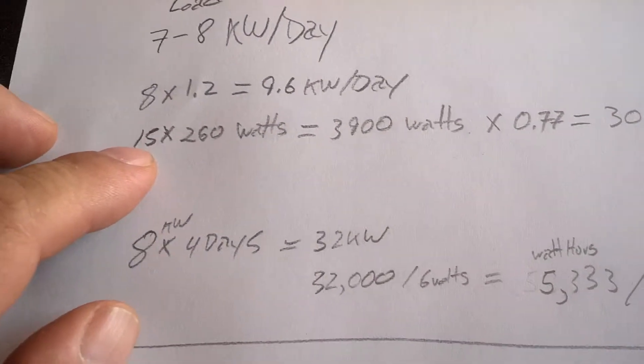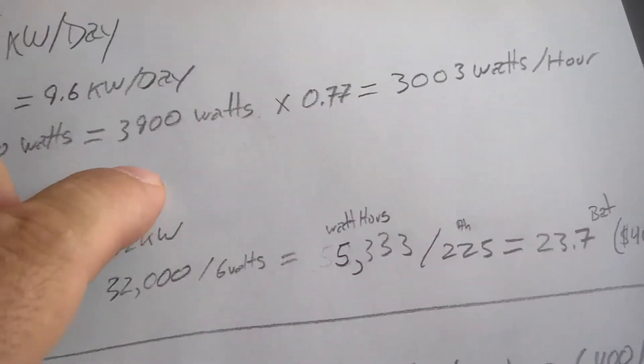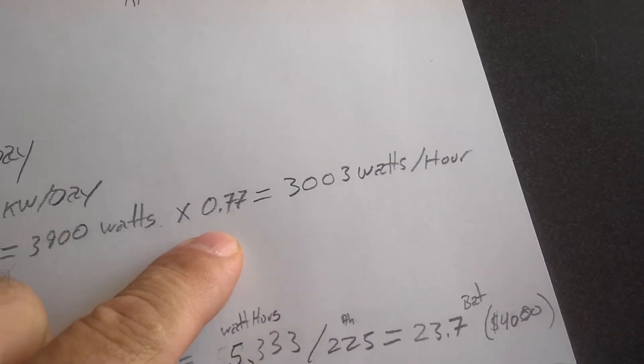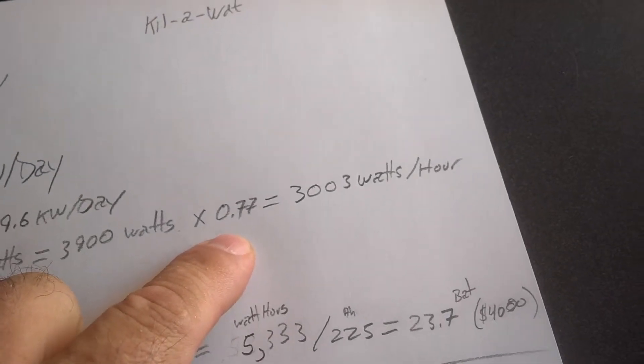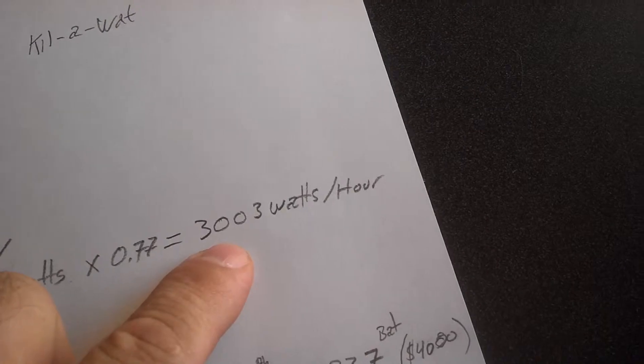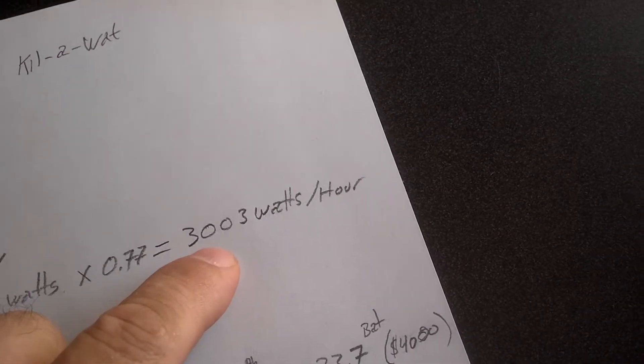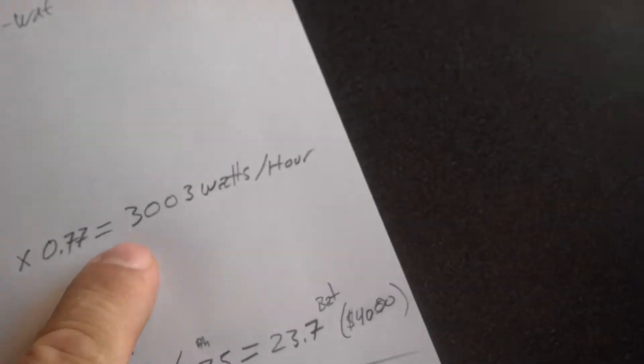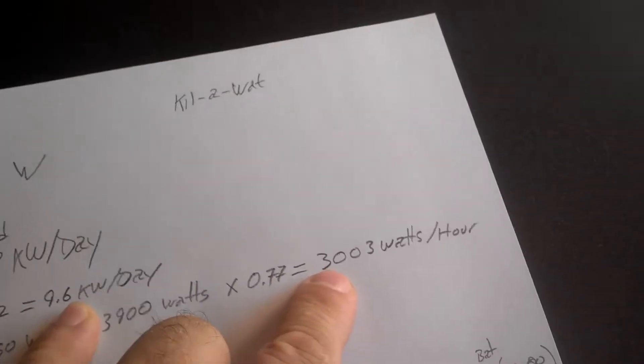If we go with 15, 260 watt panels, it comes up to 3,900. But after we derate the panels from the STC, the standard test conditions to what they really put out, they're going to put out about 3,000 watts an hour when the sun's hitting on them perfectly. So in order to get our 9.6, we're going to need at least a little over 3 hours per day.